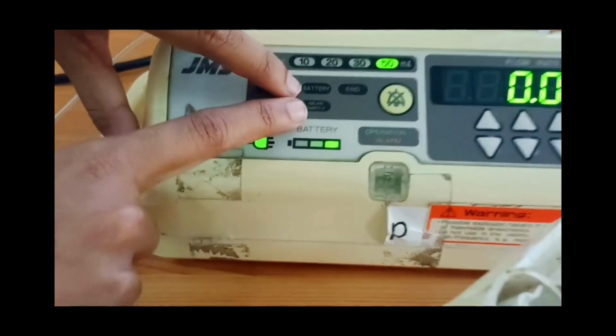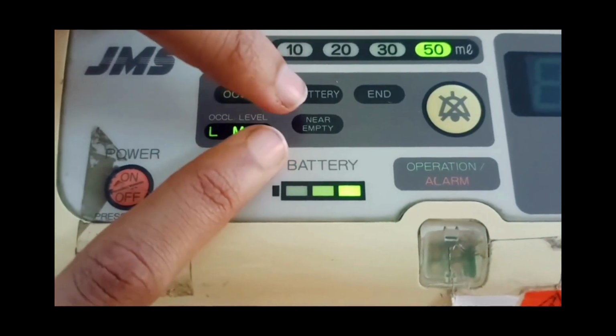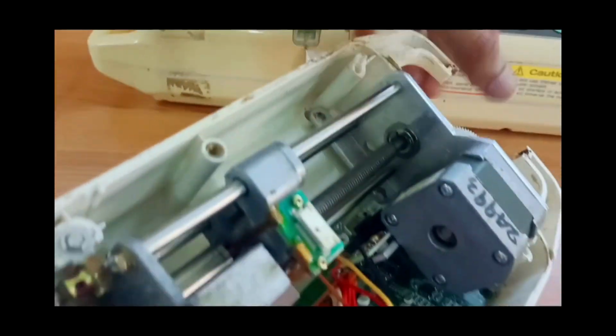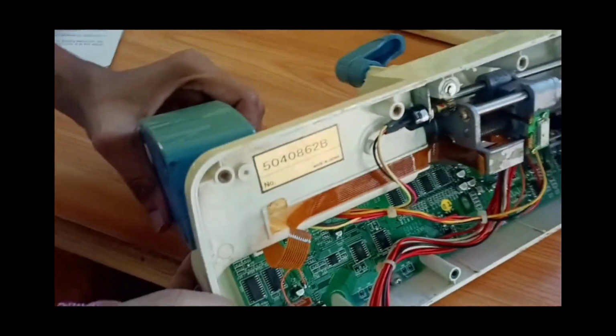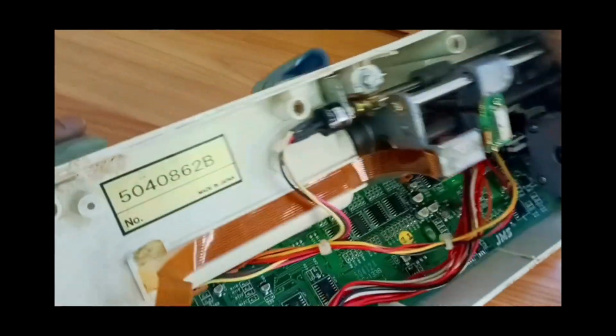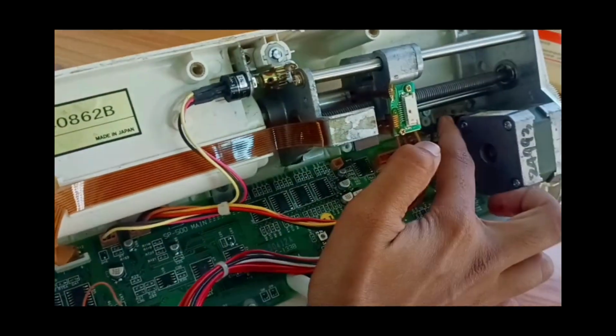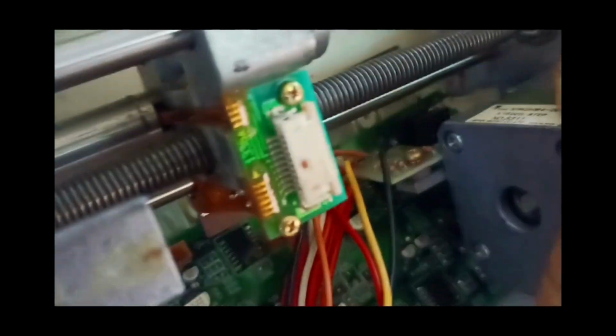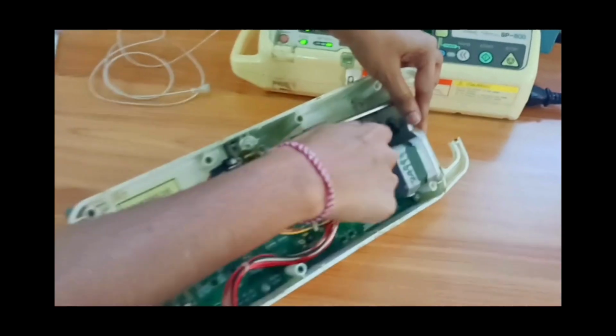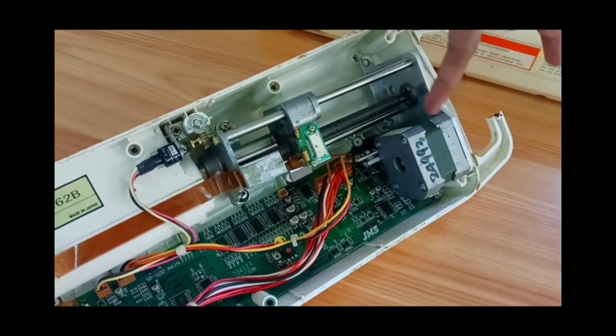This is the near empty flash. It is going to flash when the plunger position almost reaches the near empty sensor; then it will sense it and that alarm is going to flash. And at the bottom of the syringe pump stepper motor, we have another sensor which will detect the end position.